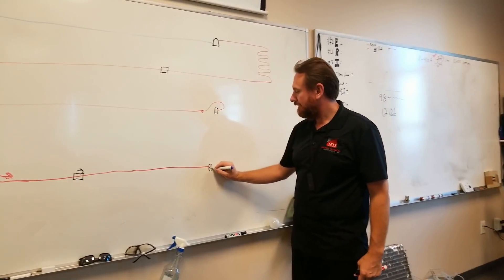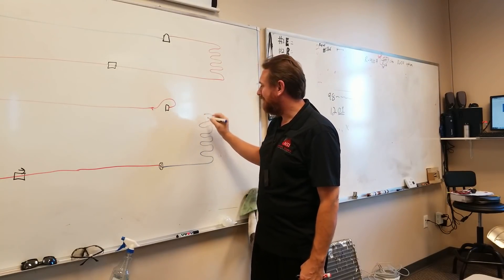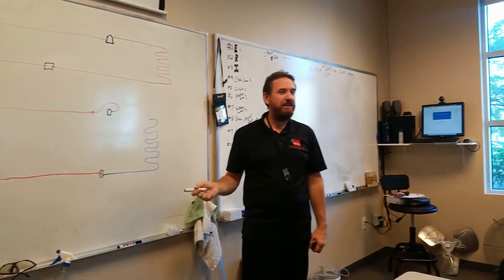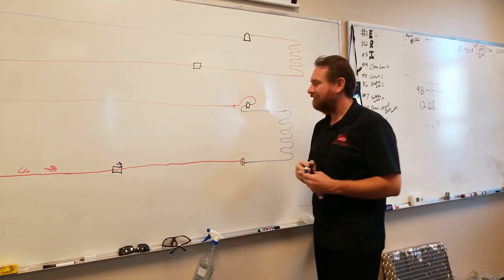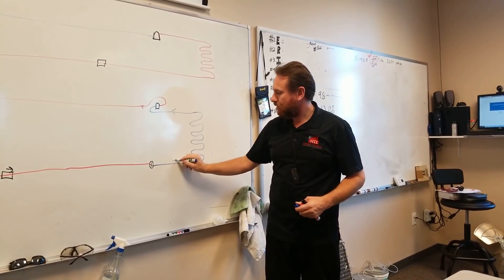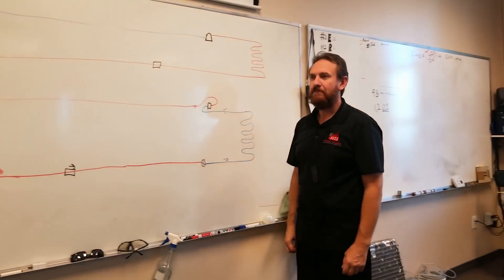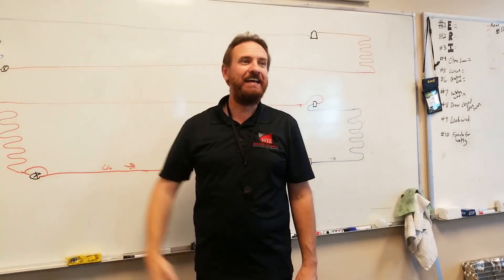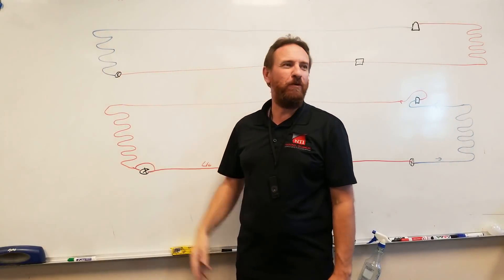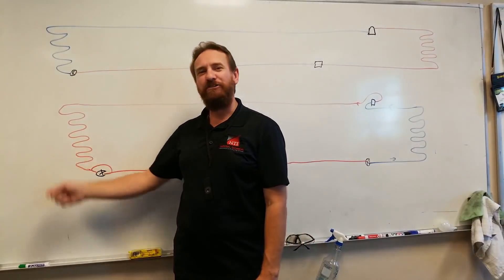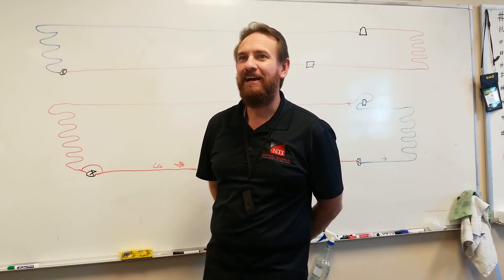My pressure drops, low temperature, low pressure. Then I had my coil — the refrigerant would be lower than the temperature outside, boiling from a liquid to a vapor. I took that pipe and connected it to the same incoming pipe side of the compressor. I would be rejecting heat inside the house. The temperature of this coil would be warmer than the air temperature, and as I move air across this warmer coil, the heat would be leaving the refrigerant and going to the air — the air would be heating up.